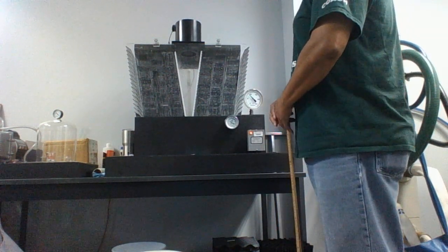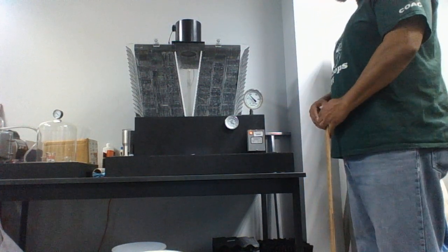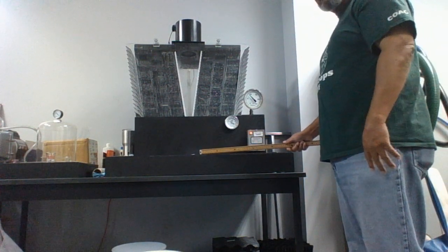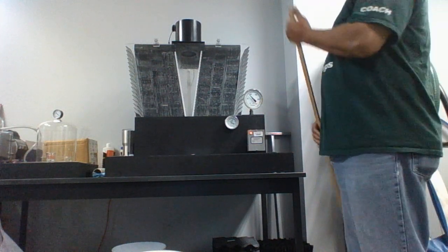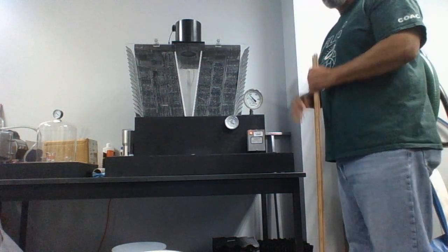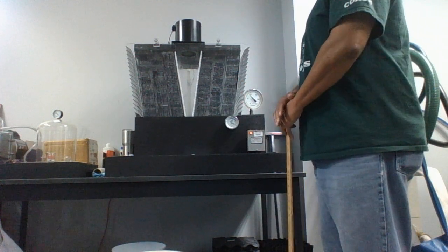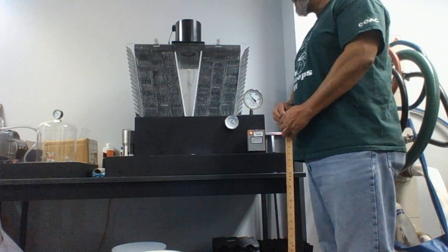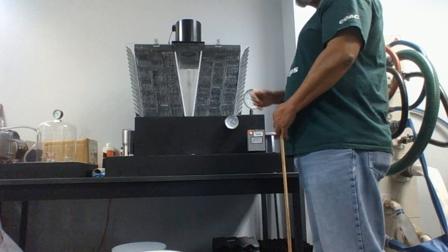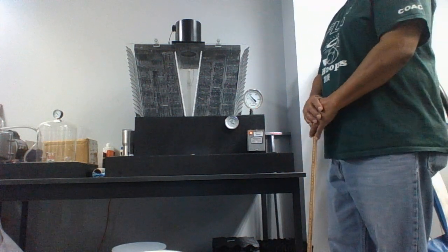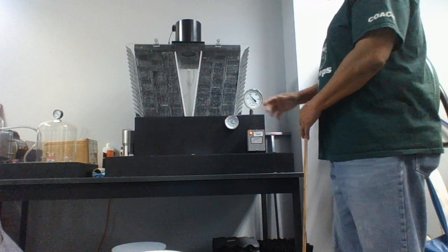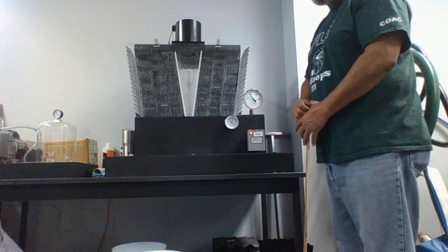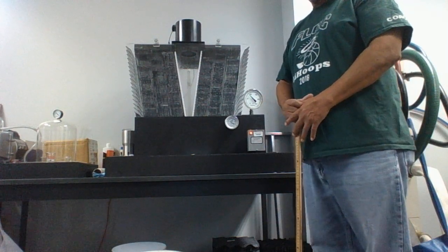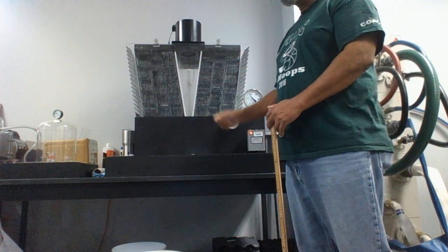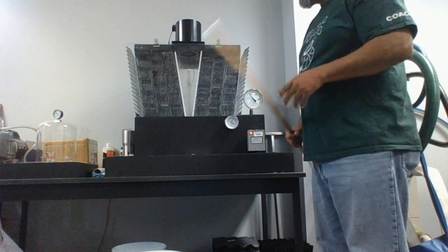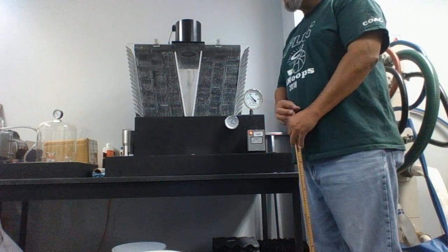As an operator, your concern is to make sure when you come in making your rounds, you check your pump, check your suction and your discharge pressure on your base pump, and you also want to go on top and check your oil levels and check for vibration on your gearbox and your motor. Then basically in the winter months you have to be very careful because you do develop ice. So when you're going up, you have stairs leading from the ground to the very top of your cooling tower. Be careful on the steps and use caution going up and down because there is a trip hazard.